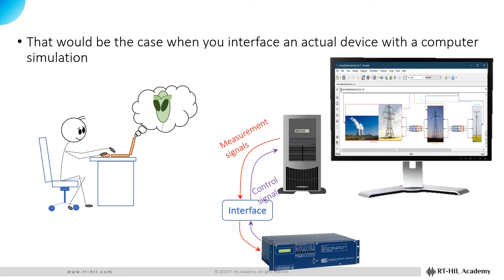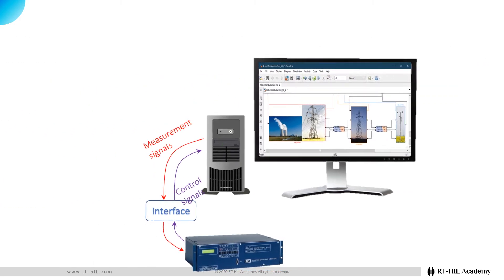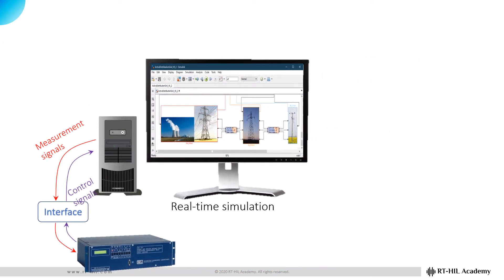In this example, the actual device — which might be, for example, a controller or a protection relay — represents you. Likewise, the computer simulation represents the UFO. The time progression for the device is ruled by real-time, whereas the time progression in the simulation is governed by the simulation engine, which can be either faster or slower than real-time. So, if we want the device to properly interact with the simulation, we should make sure that the simulation runs in real-time. This is where the real-time simulation is needed.